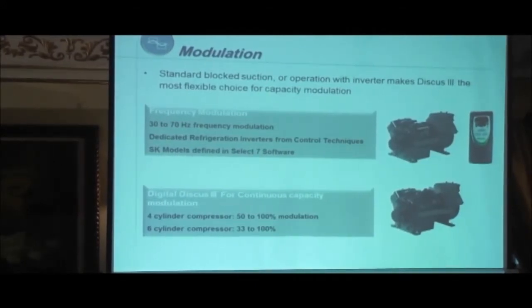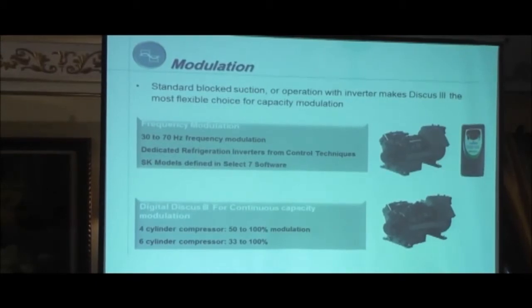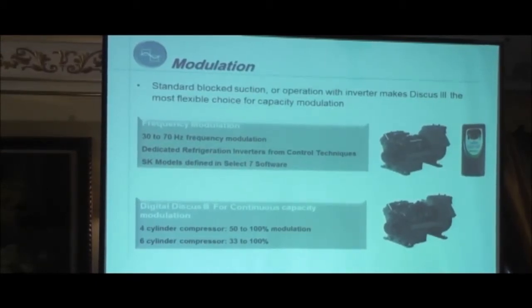In terms of modulation or capacity control, we are still keeping with capacity or block suction, where we block off one cylinder to regulate the output capacity of the compressor. So that remains. What we have done though is we've changed the design of the motors so that they can work with frequency converters or VFDs, to increase the reliability of the motor with the frequency drives. With the new compressors, if you apply a frequency converter, you can cycle that compressor from 30 Hertz up to 70 Hertz.